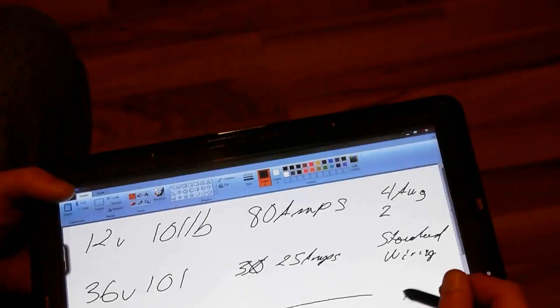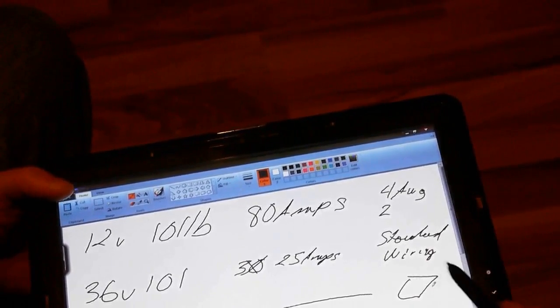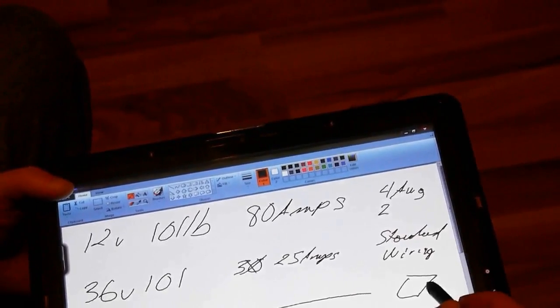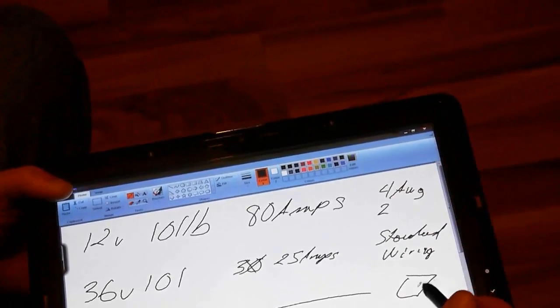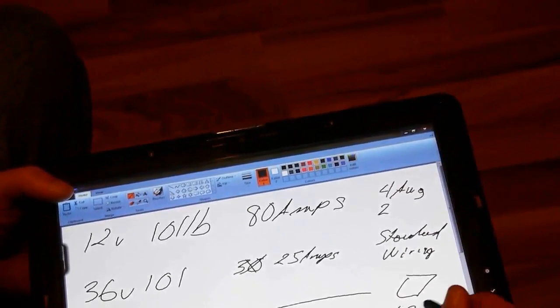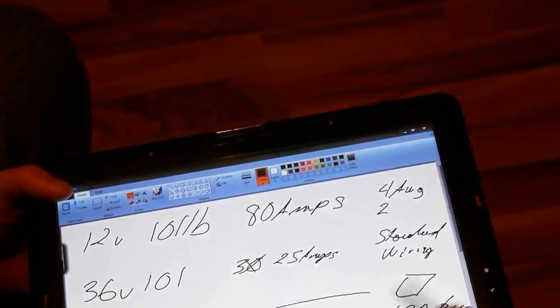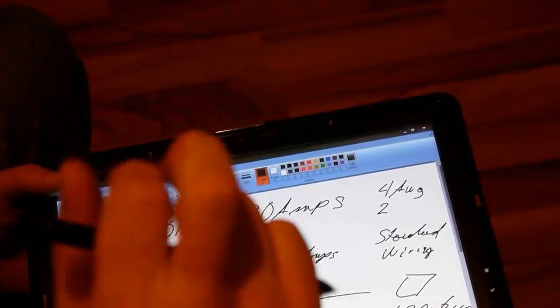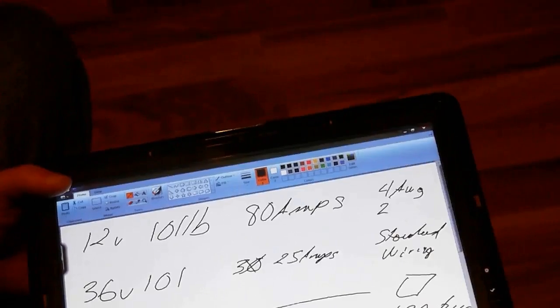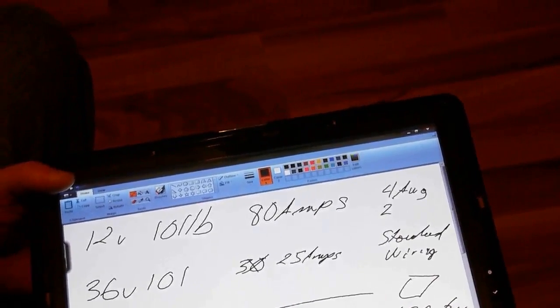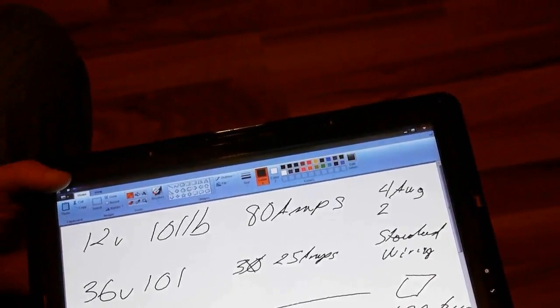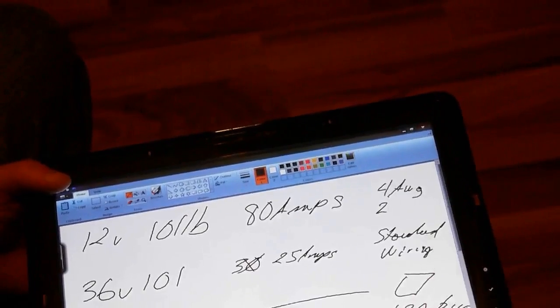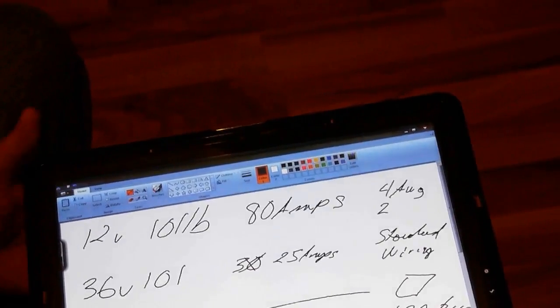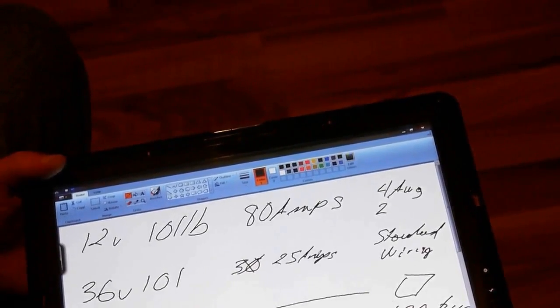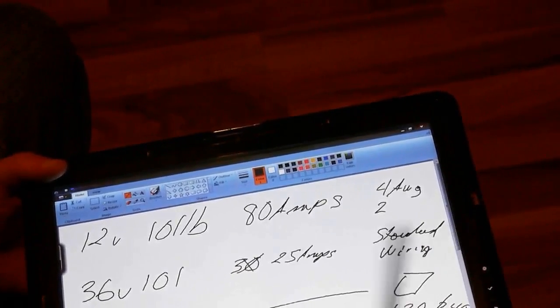Now once they convert it, notice that transformer on your pole supplying your house - those little lines come into the transformer and it steps it down to 120, 240 on different legs. And those cables coming to your house are a lot bigger. Our voltage drops because we don't want 8,000-10,000 volts coming into our house. So they step that voltage down, thus the cable size gets bigger - they go to like an aught size cable that comes into your house. So that's the theory behind why manufacturers go up in voltage.